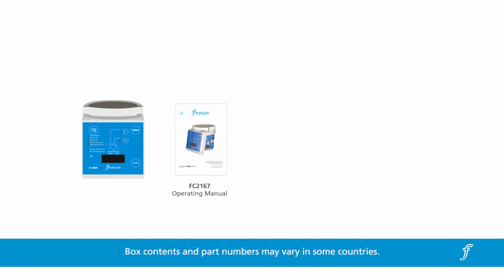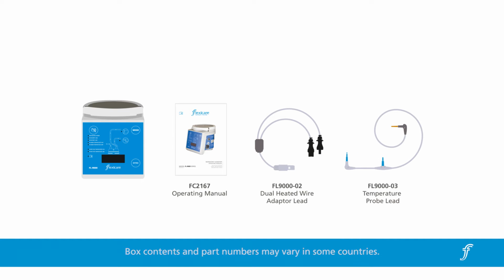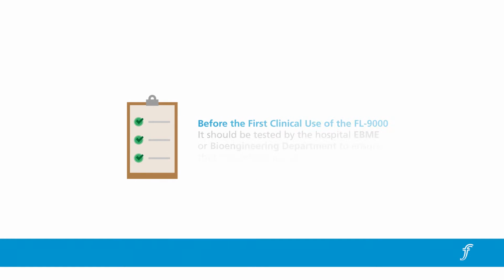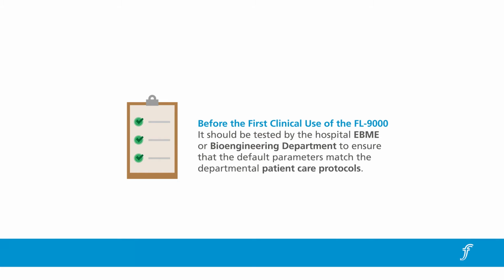The FL9000 respiratory humidifier is supplied with the following: an operating manual, a dual heated wire adapter lead, and a humidifier temperature probe lead. Before the first clinical use of the FL9000, it should be tested by the hospital EBME or bioengineering department to ensure that the default parameters match the departmental patient care protocols.